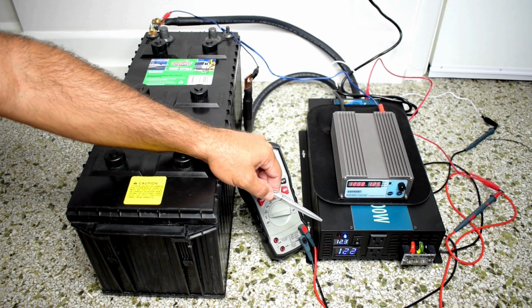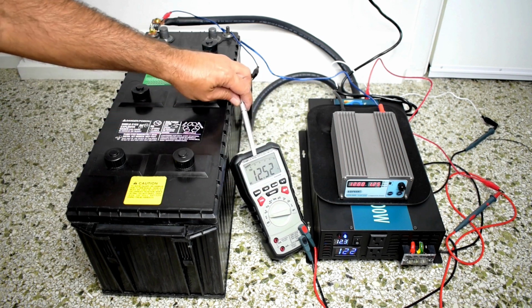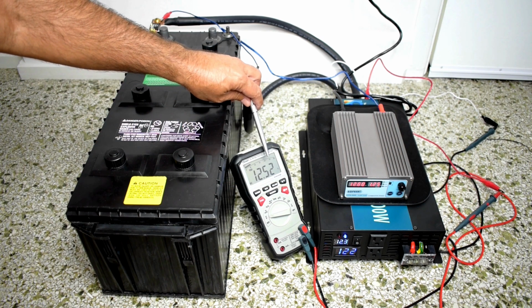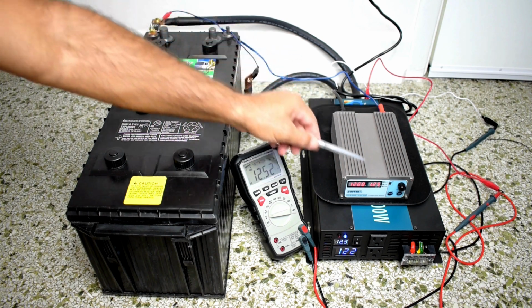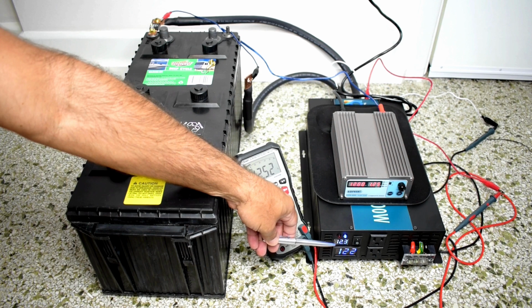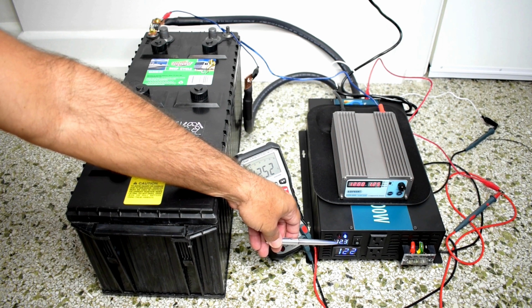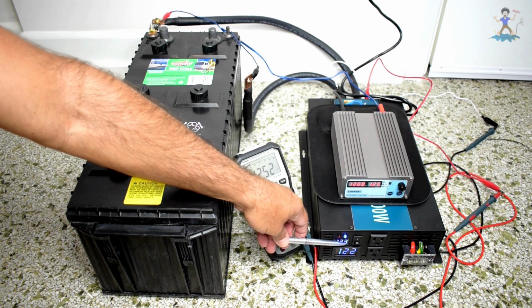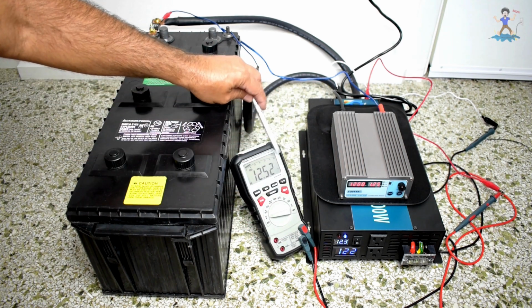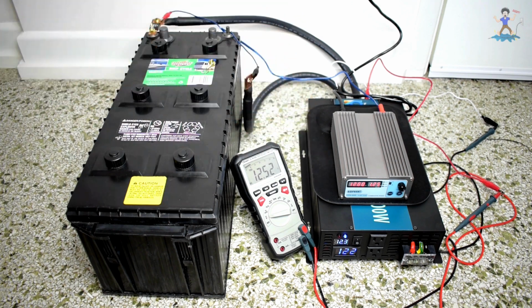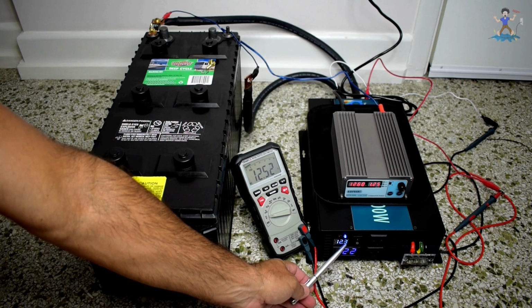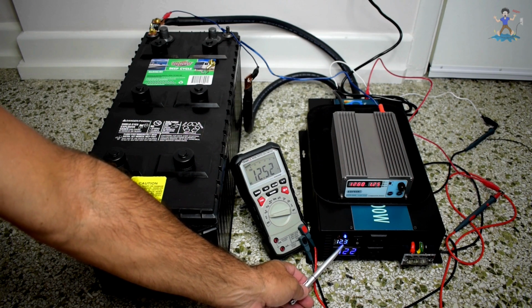122 volts. The test I'm going to do now is the low voltage DC and high voltage DC cutoff test. Over here you can see we're showing 12.52 volts DC. The battery's disconnected, and we're taking the power directly off this power supply unit, so it's 12.5, 12.5, and we're coming in a little lower on the reading here. It says 12.3, so not really critical, but it would have been nice to see a little better accuracy on this reading. After all, the reading I'm taking right here is right off the lugs on the back of the inverter. So this one here is high accuracy, and this one is off just a little bit. Remember, this could be 12.34, so it could be off about 0.15.